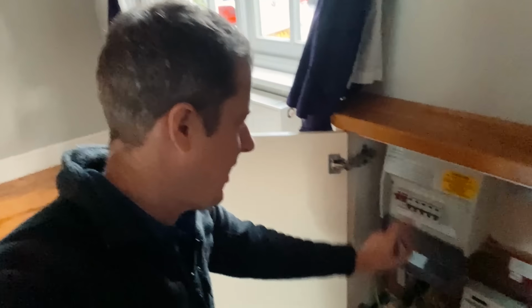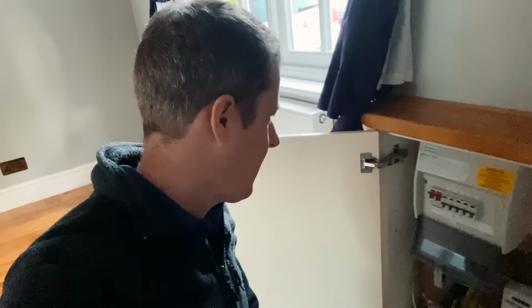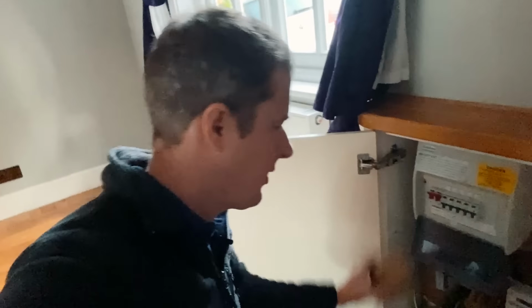So, after last night's craziness with that long job with the chargers for the scooters, now it's an early morning and I'm supposed to be in the studio filming today, but I've had to just jump out and do a few urgent remedial works. So I'm here in this house which basically the tenants are moving in this afternoon. And we had a couple of RCBOs in here, these Crabtree ones that are just faulty. They failed the half times test and the 5 times test. So I've got some new ones, so I'm going to just swap those out.